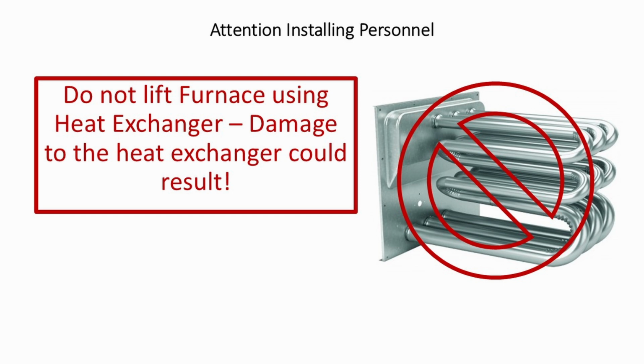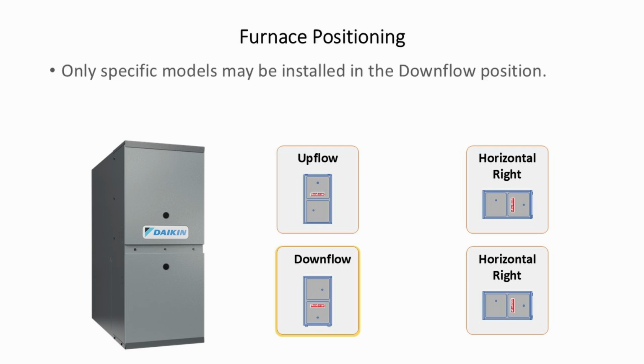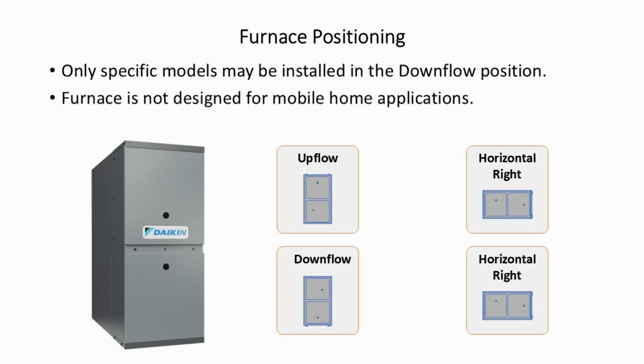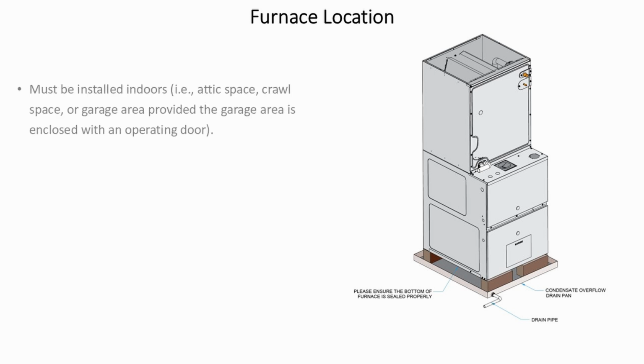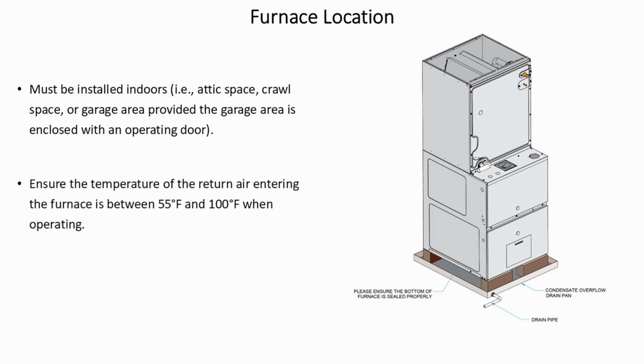Attention installing personnel. Do not lift the furnace using the heat exchanger. Damage to the heat exchanger could result. Furnace positioning. Only specific models can be installed in a downflow position. Even though there is a downflow version of this furnace, it is not designed for mobile home applications. Furnace locations. The furnace must be installed indoors, for example, attic space, crawl space, or garage area, providing the garage area is enclosed with an operating door. Ensure that the temperature of the return air entering the furnace is between 55 degrees Fahrenheit and 100 degrees Fahrenheit when operating.